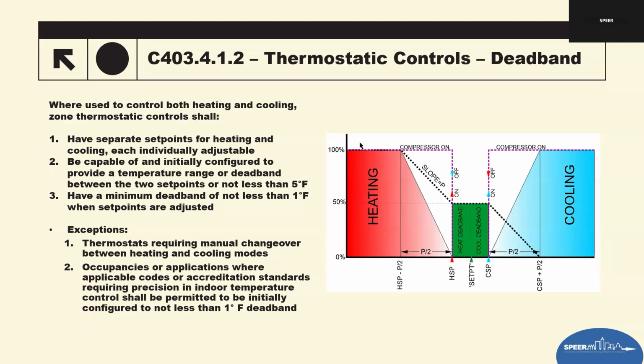So in plan review, check that the thermostat's type and sequences match and that they are capable of a 5 degree deadband. The controls narrative shows separate heating and cooling set points, and the occupancy exceptions are documented if they're claiming that. And then during inspection, verify the thermostat is actually set up with separate heating and cooling set points. The initial deadband is 5 degrees, and the adjustable deadband isn't less than 1 degree. And if exceptions are being used, the occupancy type matches what's allowed in the exception.